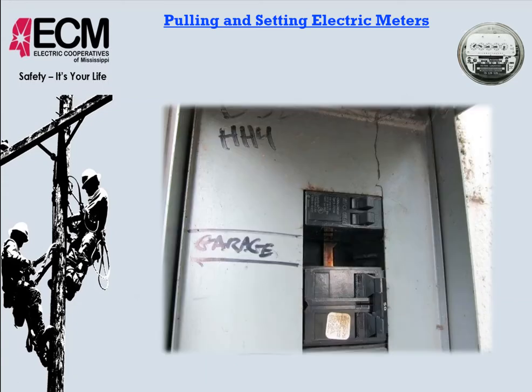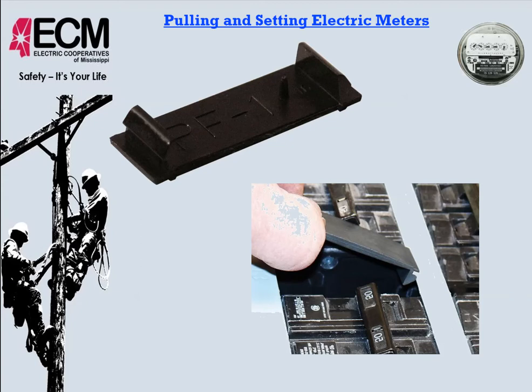Okay. Another thing we're going to look at while we're inspecting this meter base and the breaker box that goes along with it, if it has that, is open spaces for breakers. That's something that needs to be fixed, needs to be covered up, and they make little blanks for those. It's just a little plastic tab. Never seen a metal one, but plastic tabs have the little keeper flanges here, and they just push into there, and making sure that that is closed up. There again, we don't want anybody to get injured in there, and also we don't want insects and stuff like that getting in there. Wasp nest. Wasps really like to nest inside of meter bases and breaker boxes.